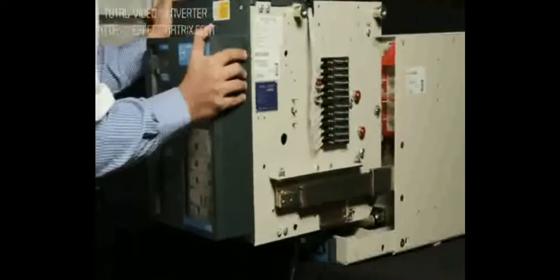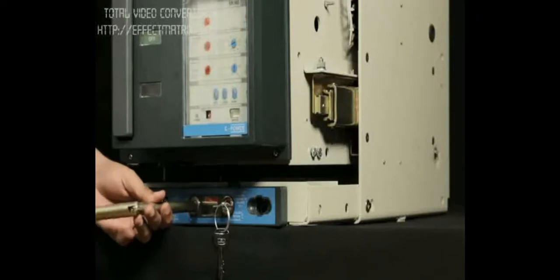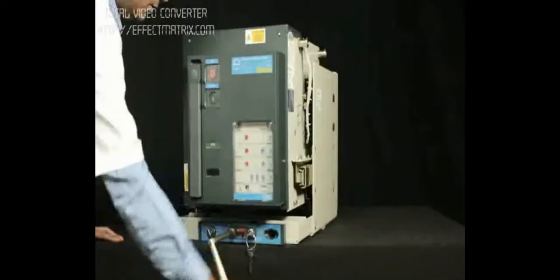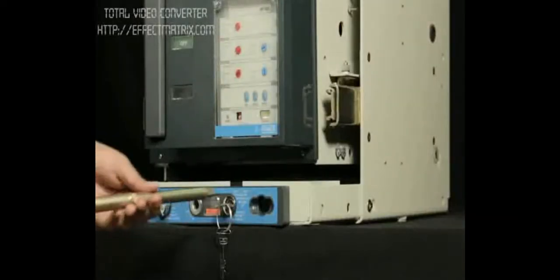Press and rotate the clamp back to lock the arc chute. Push the breaker to isolated position. Insert the handle in the slot provided for rack in and rack out. Insert the breaker to service position by rotating handle in clockwise direction.